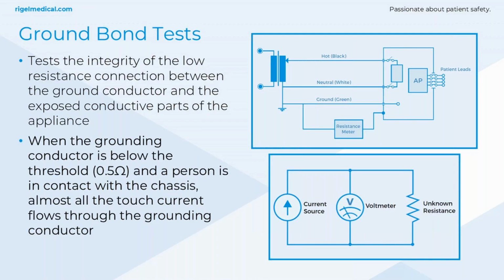And I would like to explain it like this: the human body's resistance is about 1 kilo ohm. So even at the maximum value of 0.5 ohms in NFPA 99, that in theory means that 2,000 times less leakage current will flow to the human body without ground bond. So that's the way it performs the safety test. It allows the leakage current to have a much easier path to flow back to ground.